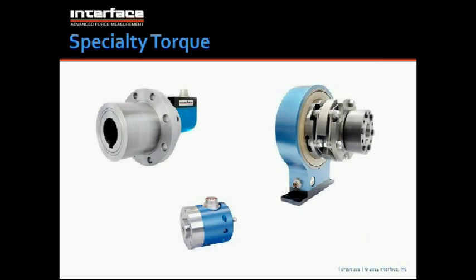Here are some examples of specialty torque sensors. Again, shaft and flange style are very common, but in some cases they're not necessarily the best approach. For example, if you want to measure pulley torque, it can be difficult to do that with a regular type sensor without having to install a bunch of different bearing blocks and things to support the radial load from the belt. A pulley torque sensor accommodates that. You can see up here on the left is a pulley torque sensor. The sensor would mount onto a motor shaft or a shaft, and then a pulley mounts to the sensor, and you can actually measure the applied torque through the pulley into the shaft.